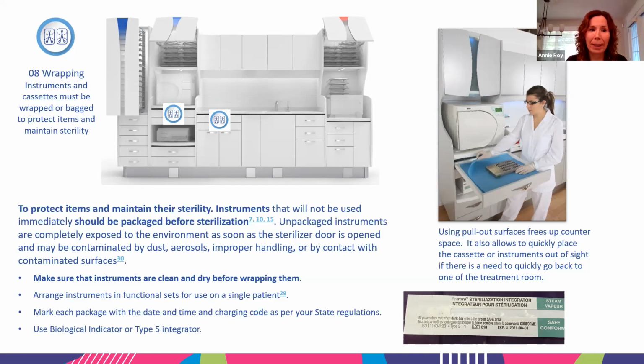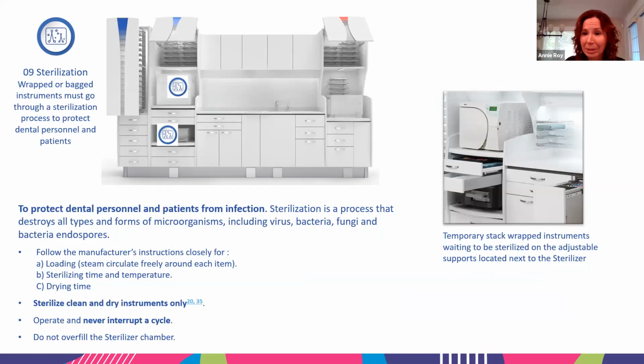So of course, after wrapping, the obvious next step is sterilization. So use the autoclave, use any types of equipment you have. We are always recommending to temporarily stack wrapped instruments waiting to be sterilized on some supports right next to the autoclave. So that way, when the assistant passes in front of the Steri Center, they have a visual reminder that some instruments are ready to be autoclaved. Because we know that the volume of the autoclave has a certain limit. So we don't want to overstock, do not overfill those chambers, but you want to know that you have instruments waiting to be autoclaved. So of course, Doug knows a lot about autoclaves.